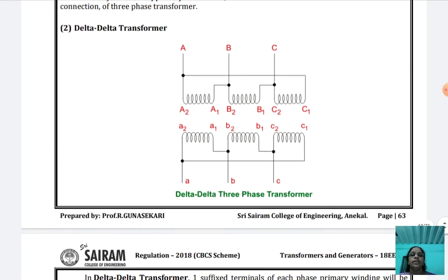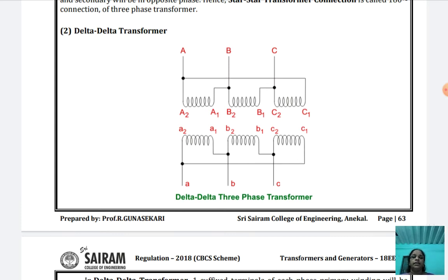Now you see the delta connection. In the delta connection, the starting end, that is A1, whether it is small a1 or capital A1, no problem. The starting end of one phase is connected to the finishing end of another phase. So A1 is connected to B2, B1 is connected to C2, and C1 is connected to A2. This is the delta formation.